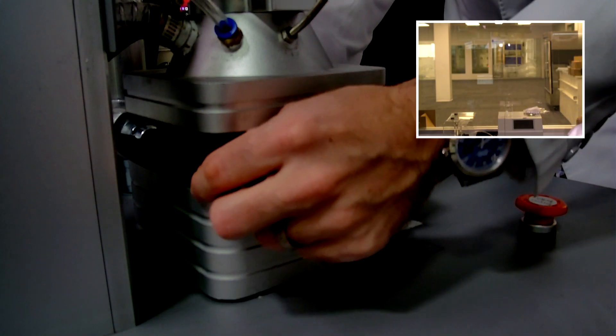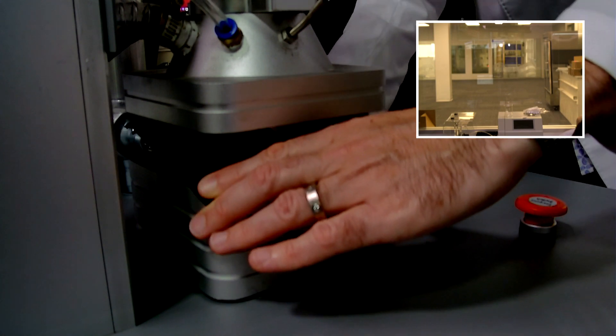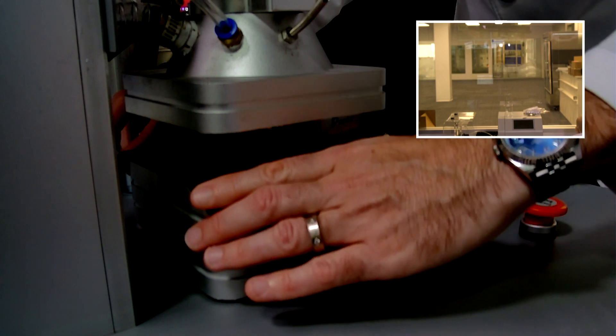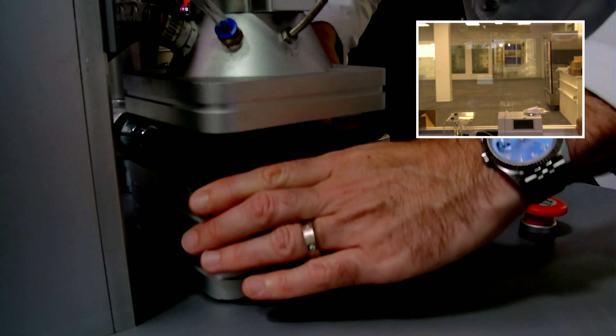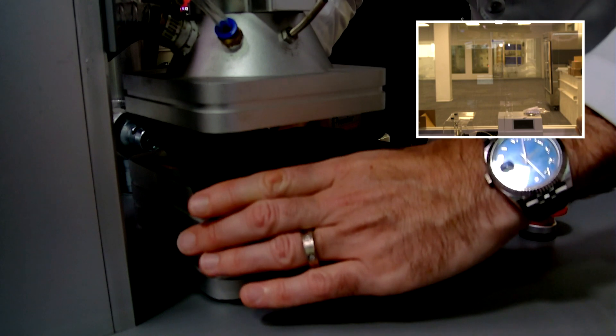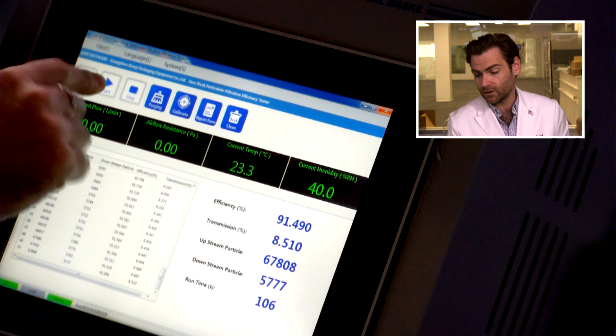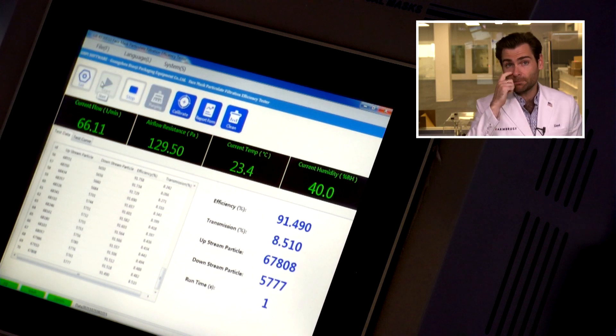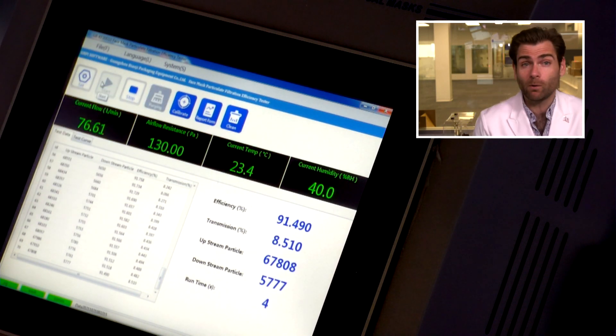It's a very thick mask. For the longest time I could not find any masks at Walmart — the only masks I could find were the ones they would hand to you going in the door. That worked! This is a PFE machine — particulate filtration efficiency machine. If you want to find out more about what we're doing here, I'll put a link up there. But the short answer is we are doing the American surgical mask test, which has a minimum standard of 95%.